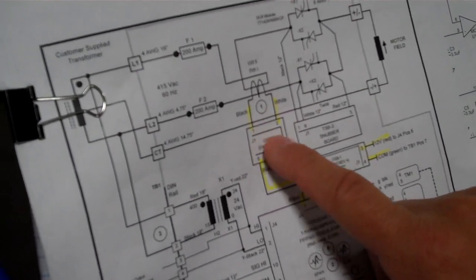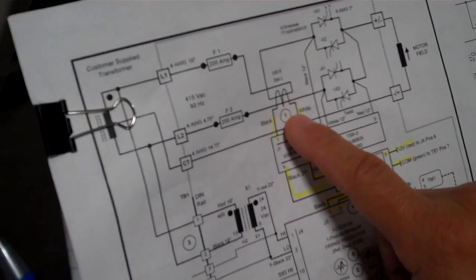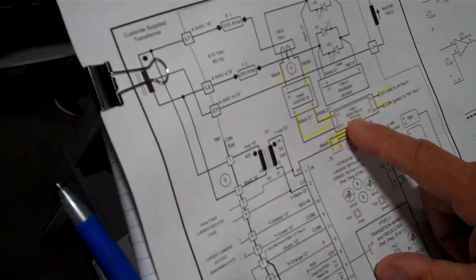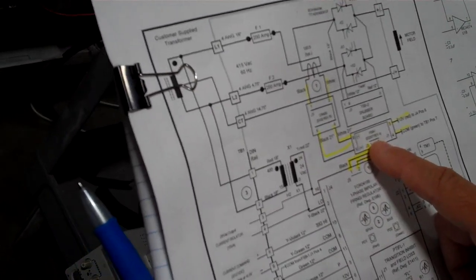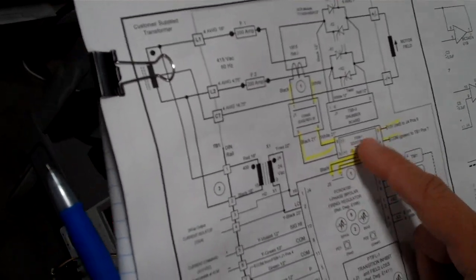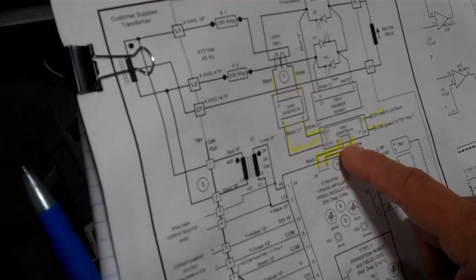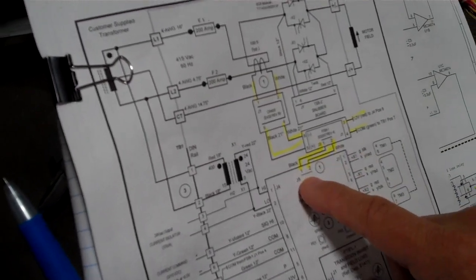This circuit rectifies the current from the CT. We use a burden resistor to get a voltage that is proportional to it. We send that to the FSB, the scaling board, so that we bring in 0 to 1 volts into J5 positions 1 and 2.